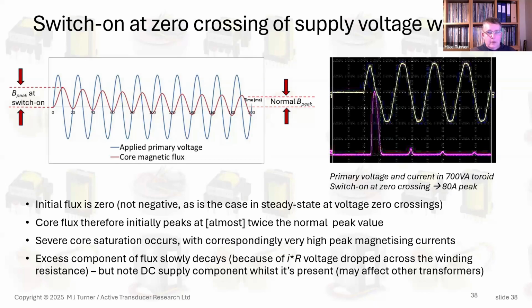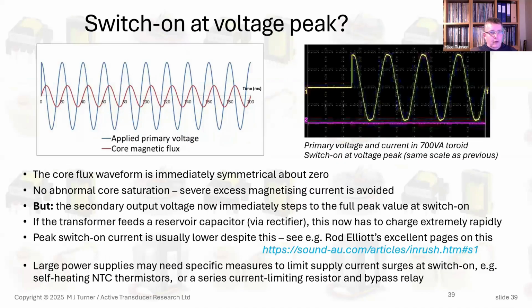And that's an example of a real one. I measured that in the lab myself. It's a toroid 700 VA, so its continuous current rating would be 2 or 3 amps on the primary. But it's got an 80 amp switch on peak. Ouch. Unfortunately, although we can fix that by switching on halfway through a half cycle, switch on at the peak of the voltage, and you can see there that fixes this beautifully.